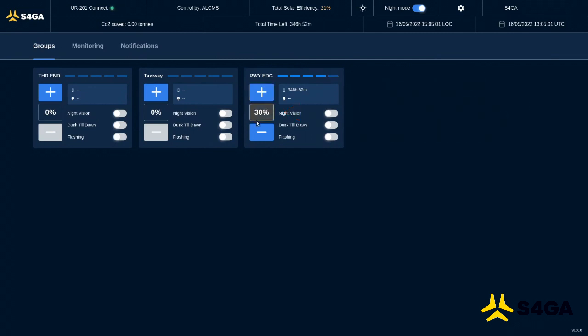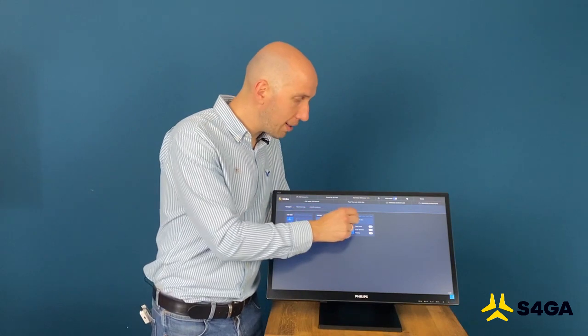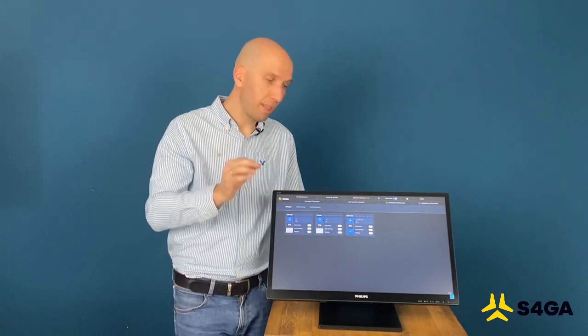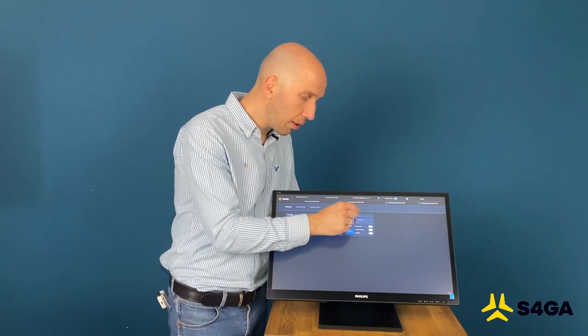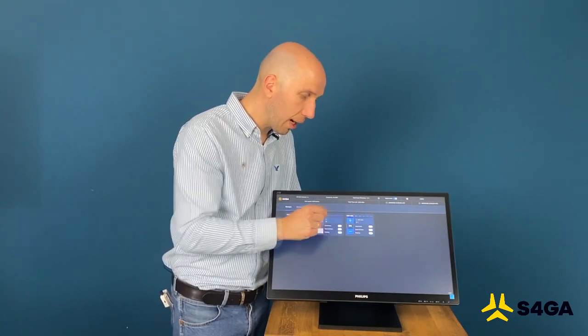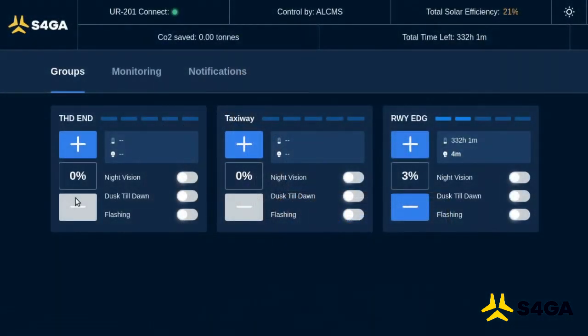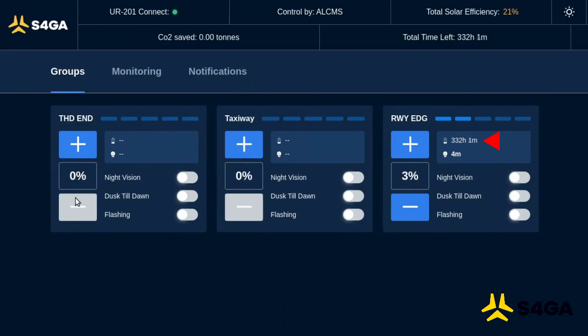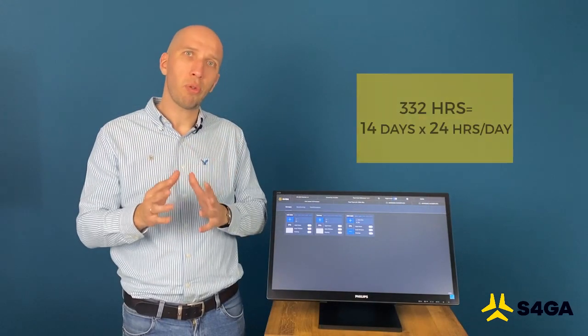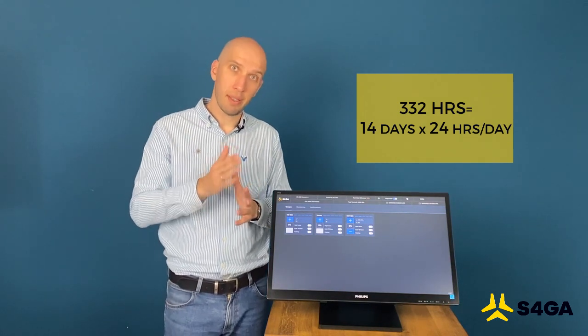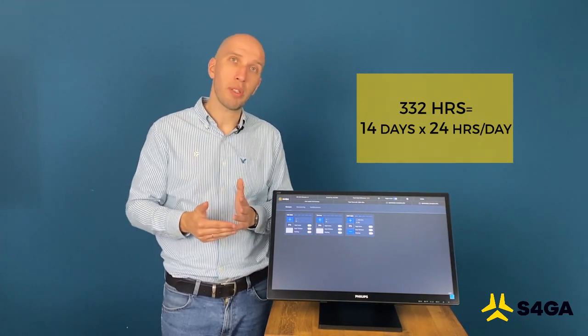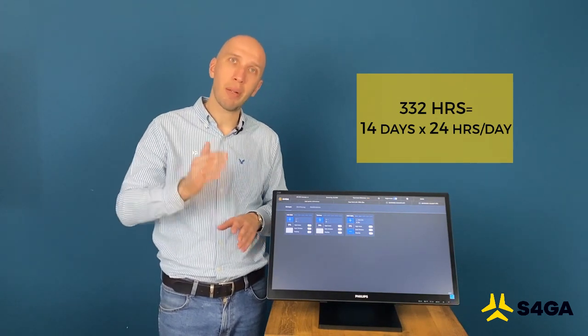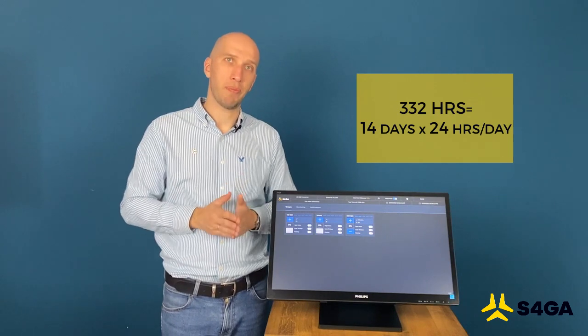Now, another very valuable feature is the operating time left on the given intensity. As you can see right here, on the right from the plus sign, there are hours that are automatically calculated when we activate light on given intensity. So what kind of conclusion can be made of this information? For example, 332 hours. Is it long or is it short? Well, for the airport it means safety. Because 332 hours means 14 days, 24 hours days, continuous operations without any charging, without any power supply. Airport can operate constantly without interruption.